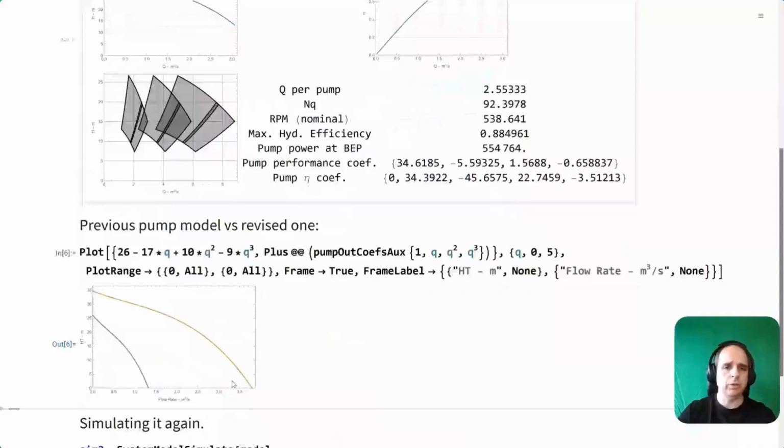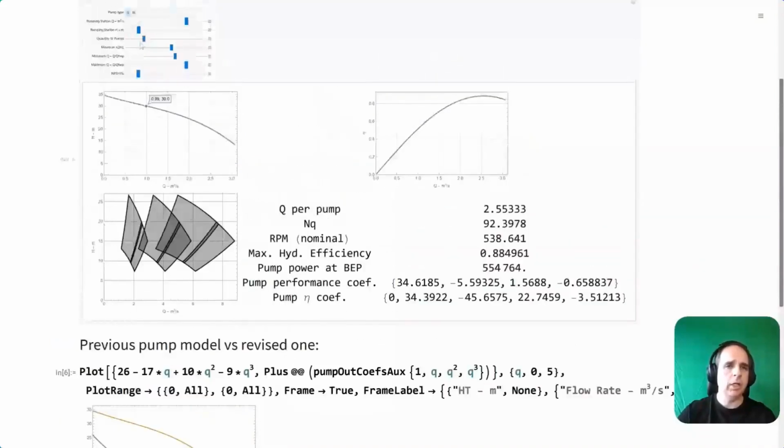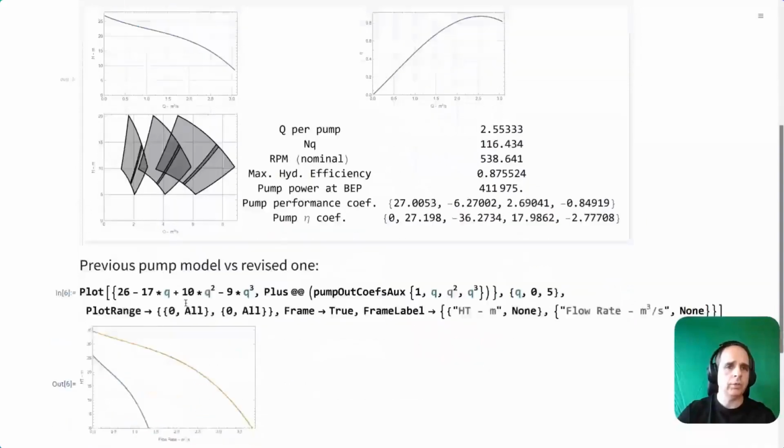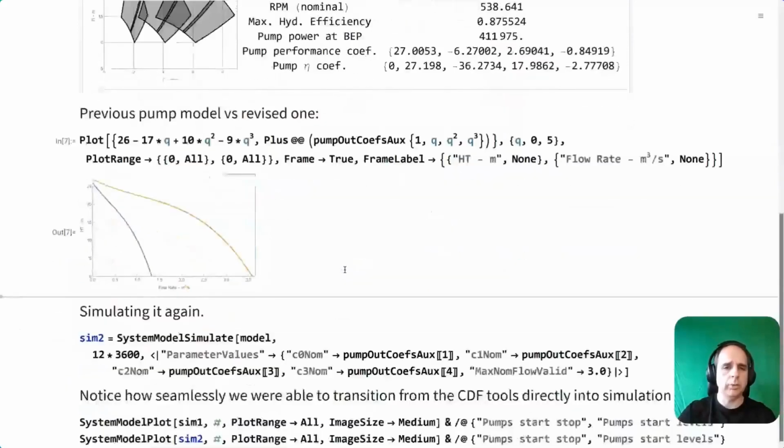The one on the right side supplies flow rates that are like 2.5 times bigger and a little bit extra head than the previous one. I'm actually going to choose a head that is a little bit lower than I had chosen. Okay, something like this seems to be a good choice for our system, yes.